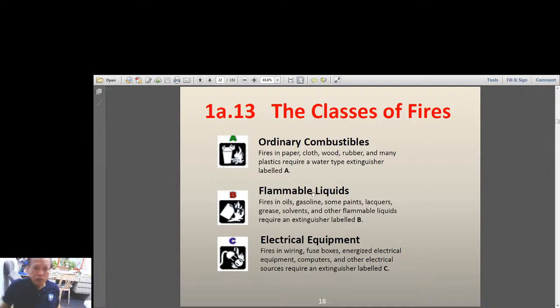Okay, so here are three ordinary combustibles. You have type A fire, caused by fuels like paper, cloth, wood, rubber, plastics, and they would require water to extinguish it. So they are labeled type A. And type B are those that are flammable substances including oil, gasoline, some paints like lacquer paints or paint thinner, grease, solvents, kerosene, LPG, and even natural gases like methane and so on, no? And letter C is electrical equipment fire. So when you have arc flash, when you have electricity that would jump from one line to the other, like a short circuit, then that is class C fire. And for class C fire, you do not use water.